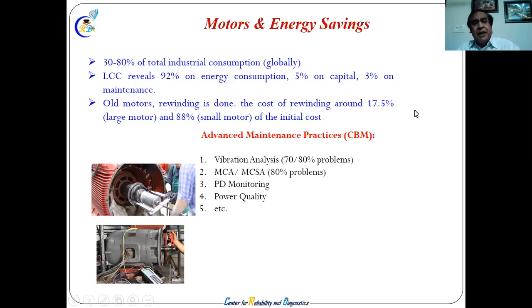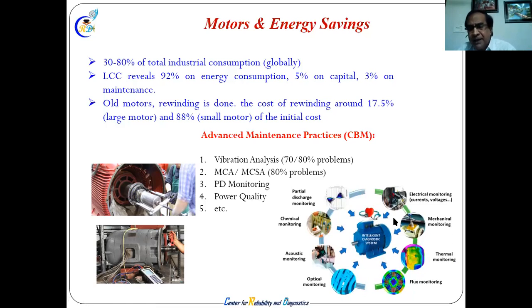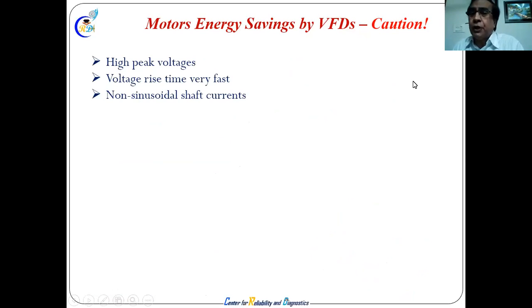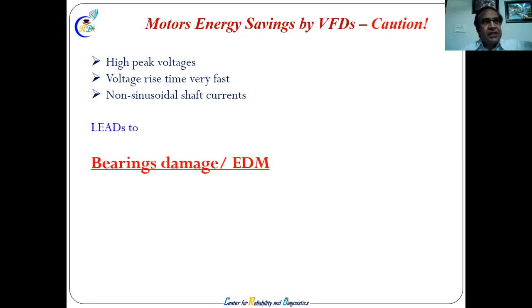You can detect these problems by vibration analysis. 70-80% of motor problems you can find out. You can also use motor current signature analysis (MCSA), PD (partial discharge), and power quality, all these things you can do. There are a lot of other techniques available for motor energy saving. Motor energy saving by VFD needs some caution. We always very easily use a variable frequency drive, and you change the speed, and we are getting a lot of energy savings. But in that process, we also damage the bearing, because there is a high peak voltage, very fast pickup, very fast down, very sudden change in RPM, all these things happening, and it takes a lot of energy.